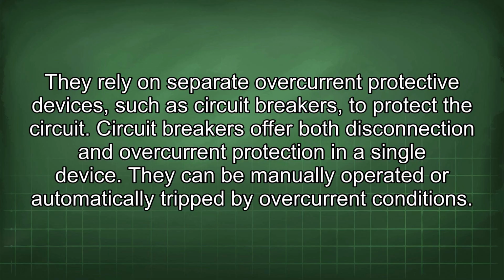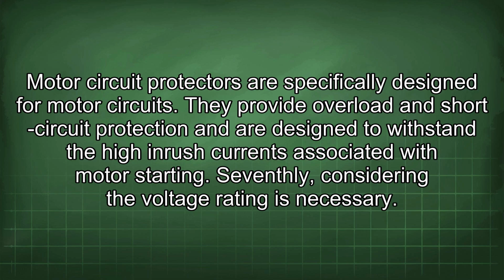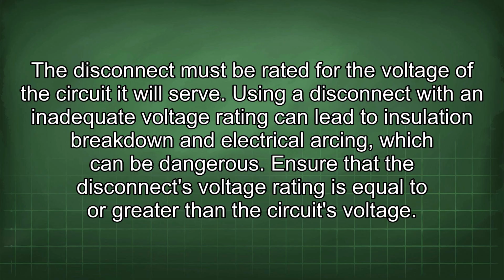Circuit breakers offer both disconnection and overcurrent protection in a single device. They can be manually operated or automatically tripped by overcurrent conditions. Motor circuit protectors are specifically designed for motor circuits. They provide overload and short circuit protection and are designed to withstand the high inrush currents associated with motor starting. Seventhly, considering the voltage rating is necessary. The disconnect must be rated for the voltage of the circuit it will serve. Using a disconnect with an inadequate voltage rating can lead to insulation breakdown and electrical arcing, which can be dangerous. Ensure that the disconnect's voltage rating is equal to or greater than the circuit's voltage.